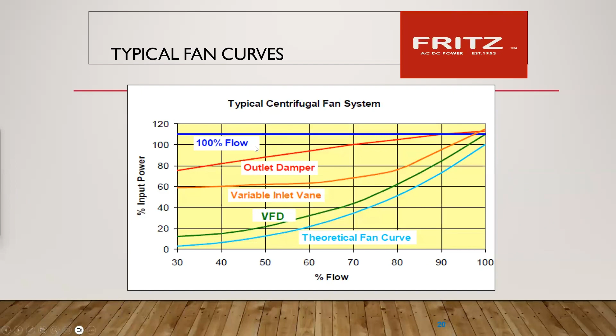And we try to take a lot deeper dive. Before, it was expensive to even buy small drives, but micro drives, a lot of them that are out in the marketplace now, are very, very reliable, and they're the size of almost a magnetic starter. So we have over the years literally done a lot of change outs of taking the motor starters out, and it does add up. And typically in the past, people were looking at, well, my avoided cost is maybe 2.5 cents a kilowatt. So is the payback going to be there?